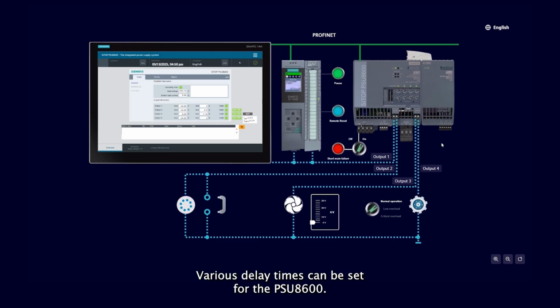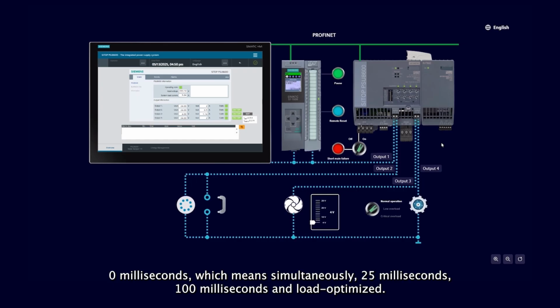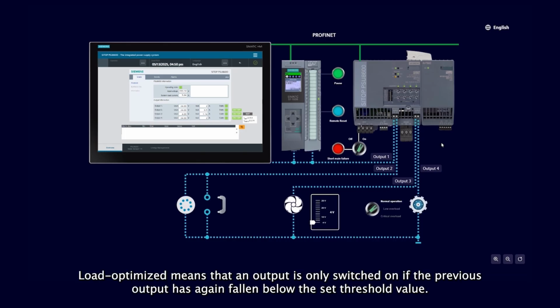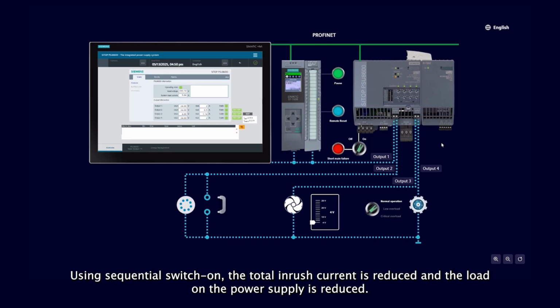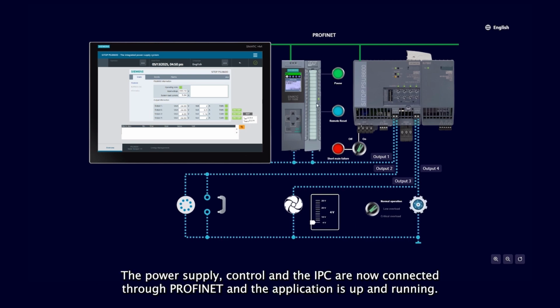Various delay times can be set for the PSU8600: 0 milliseconds, which means simultaneously, 25 milliseconds, 100 milliseconds, and load optimized. Load optimized means that an output is only switched on if the previous output has again fallen below the set threshold value. Using sequential switch on, the total inrush current is reduced and the load on the power supply is reduced. The power supply, control and the IPC are now connected through Profinet, and the application is up and running.